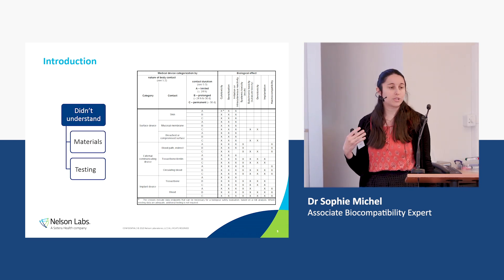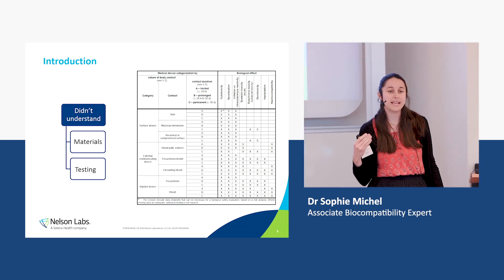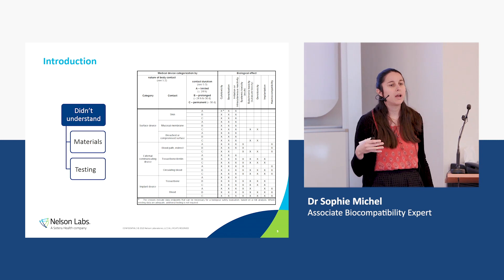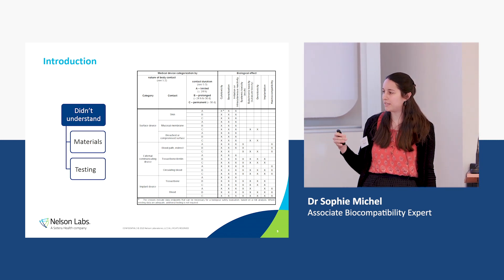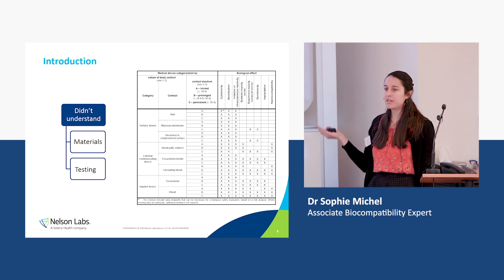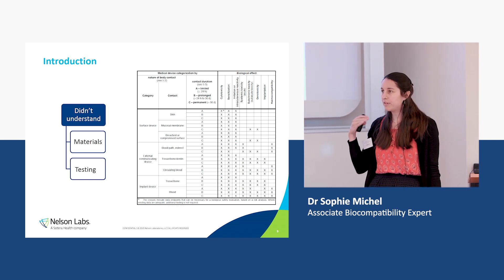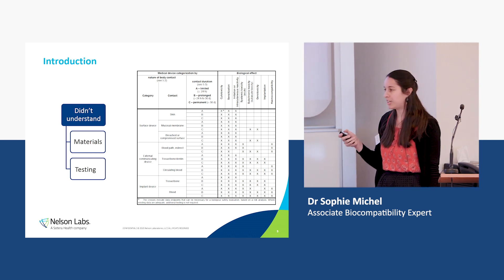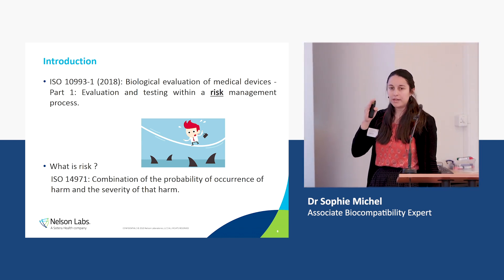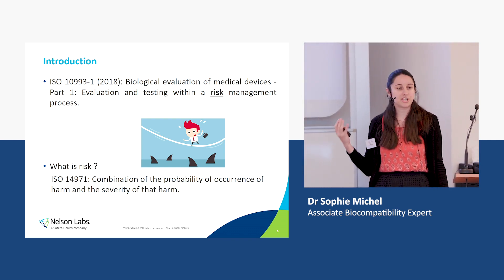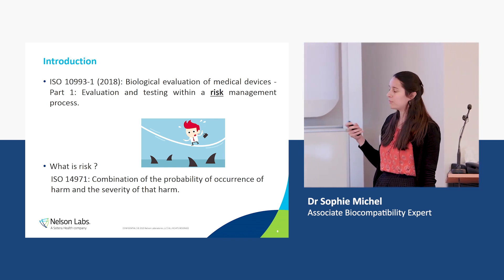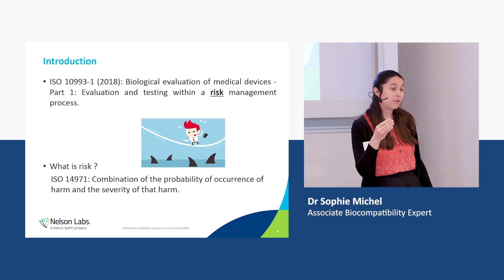The limitation was that it did not hold the manufacturer responsible for understanding their product: What are my materials? Are there standard materials in the medical device industry? What is the impact of my manufacturing process, my sterilization, my packaging? And how does my testing relate to my actual product? Because of this, there was a rethinking process in the ISO committee on how to change this way of thinking, and it came with a new title. With the new ISO 10993-1 from 2018, the content is hopefully more in line with the title.